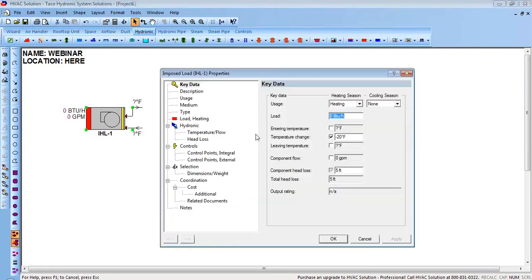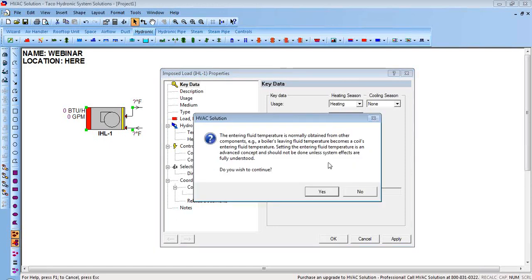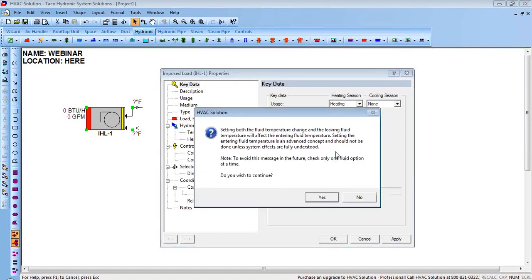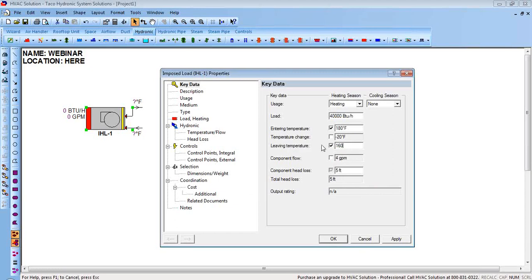Jumping back to the drawing — if I double-click on the fan coil, it's a heating-only fan coil so all the cooling data column is blanked out. I put in my heating load — let's say this is a 40,000 BTU coil. It's going to try to design it for a delta T of 20 degrees, which is traditional hydronic design. However, I personally like to put in my entering and leaving water conditions, so I'll enter 180 and 160, which is still a 20-degree delta T but locks it to those specific temperatures.